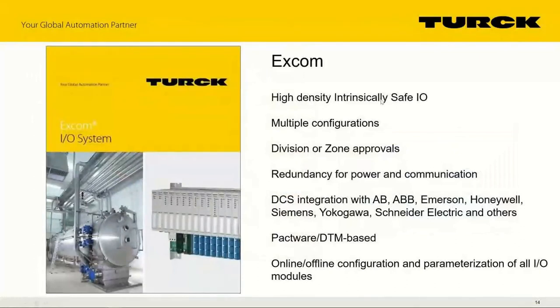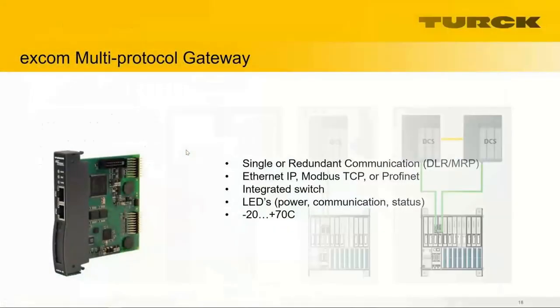For a lot of points in hazardous areas, we have our excom system — high-density I/O to use instead of many individual barriers, using a rack system. We have a new gateway that is a multi-protocol Ethernet-based gateway instead of what we had with Profibus in the past. We're waiting for our North American approval on this, but the beauty in the process area is redundancy on power supplies and redundancy on my gateway back to my DCS or PLC.